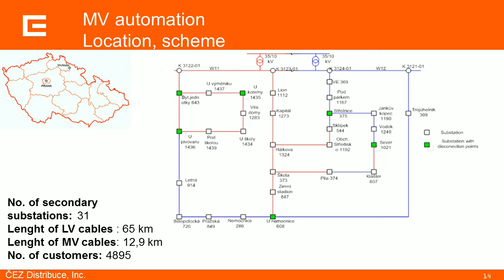So how does it look? We're doing mid-voltage automation across the whole town of Vrchlabí, which has approximately 5,000 final consumers. We've got 31 secondary substations there, and the grid topology looks like this, with the disconnection points — or disconnection substations, as we call them — shown in green. These are needed because we must disconnect the smallest possible part of the grid affected by a failure on the mid-voltage line. I'll show you on the next slide how it actually works.